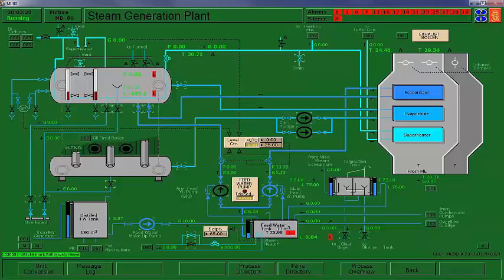Now, right now, this is in millimeters. Zero, again here on the level indicator, zero is mid-drum. Minus numbers are number of millimeters below the mid-level. Positive numbers are above. And we're going to try to get this stopped at around a minus 50. And that's about 2 inches low.